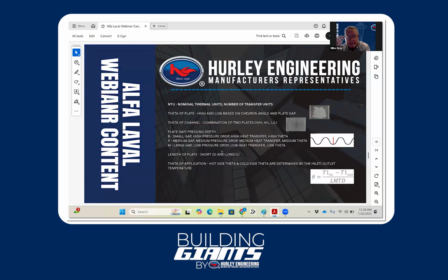Yeah, exactly. So the theta, as they call it, is all based on the chevron, whether it's a high or low angle, and you get specific plate gaps through that, as you can see there, a plate gap or pressing depth. A small gap gives you a high pressure drop, and a large gap gives you a lower pressure drop. They can mix these plates together as we make a selection, so some may be higher pressure drop and some lower within the same heat exchanger.